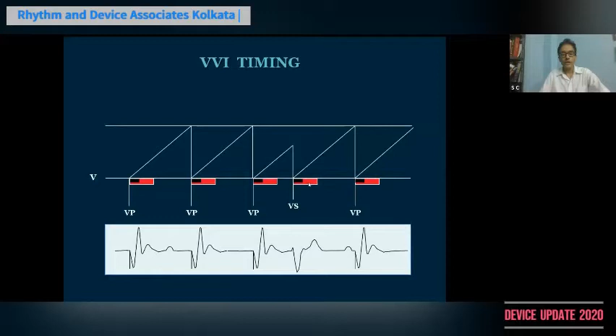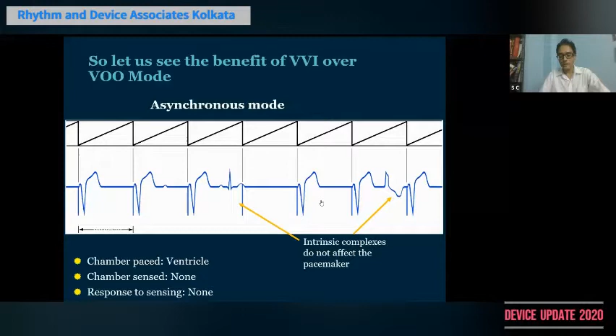So what is the difference from VOO mode? The problem with VOO mode is that it does not detect any intrinsic activity. If you see the fourth complex, it is an intrinsic activity. If the pacemaker is in VOO mode, it won't sense this activity and will give rise to a spike at the end of the base rate interval, which is marked by this arrow. However, if it is a synchronous mode, it will be sensed and you can withhold pacing till the next base rate interval occurs. So in VOO mode, you can have pacing going on in spite of whatever intrinsic event is happening. This can be dangerous because you can give a pacing spike right at the peak of the T wave. This can give rise to the R on T phenomenon, and this can give rise to arrhythmias.